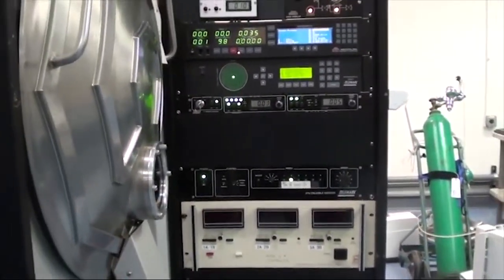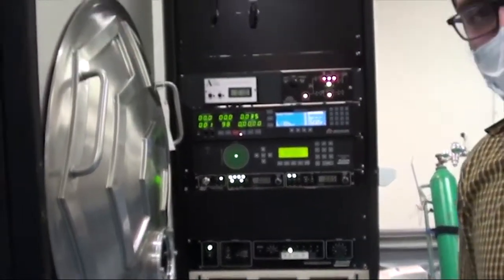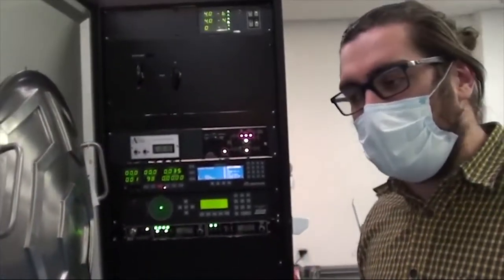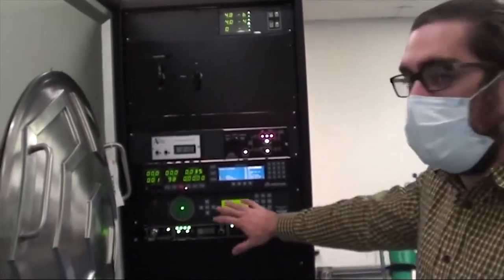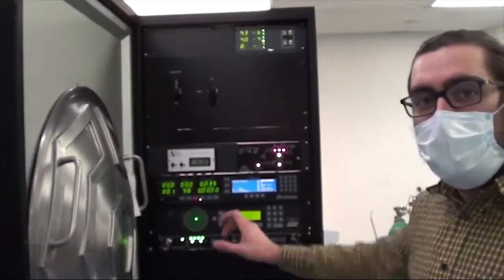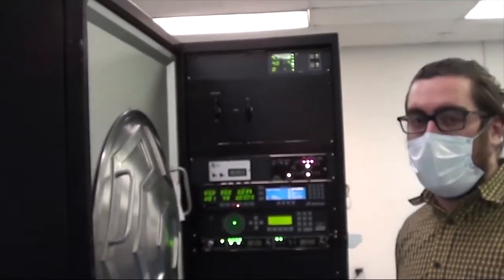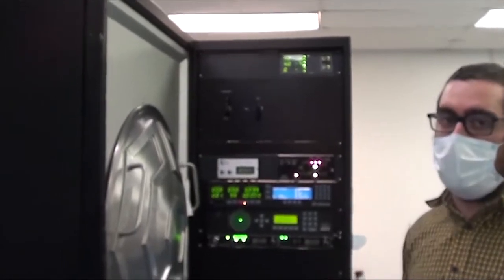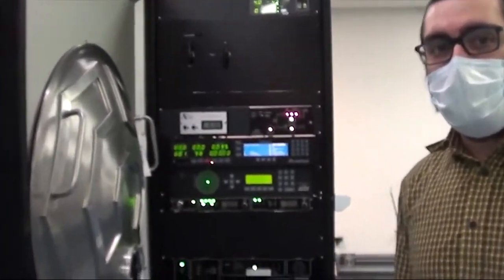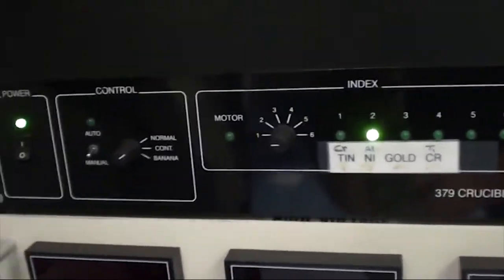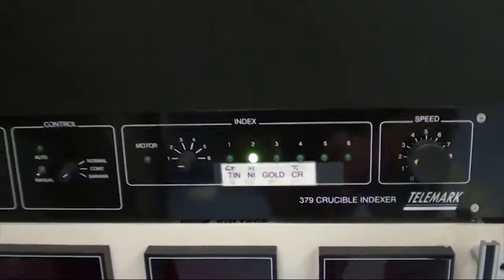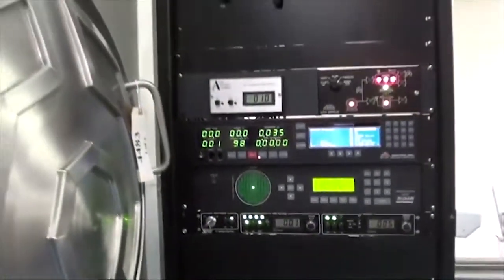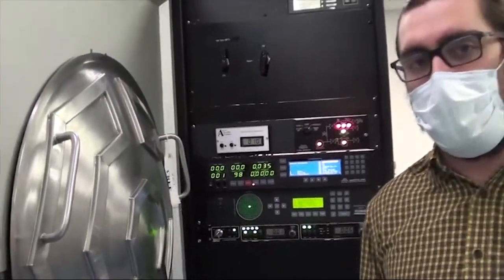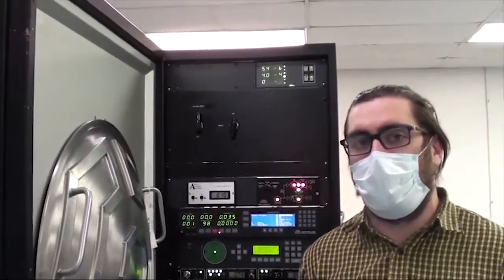And finally, there's a small adjustment that needs to be made to the E-beam to make it center onto the target. We were not able to center it with the electronics alone, so some physical adjustment needs to be made to the E-beam in order to center it in the crucible. That concludes the demonstration of the operation of the CHA Mark 40 E-beam evaporator, tool ID 4483.